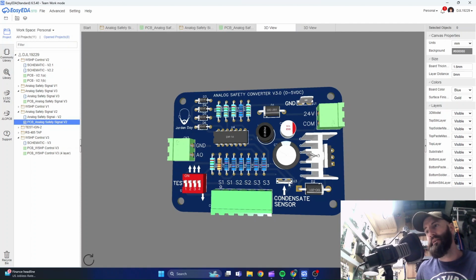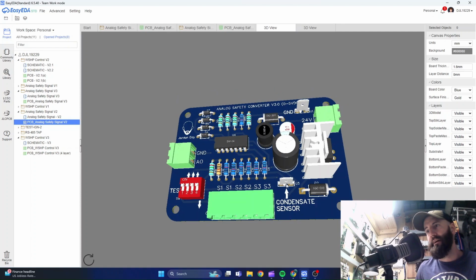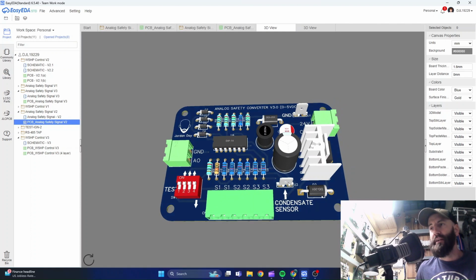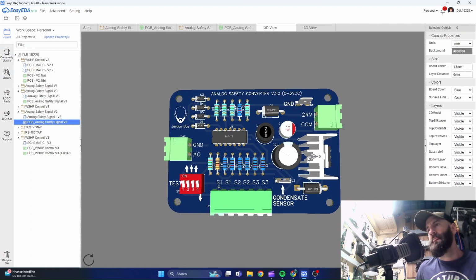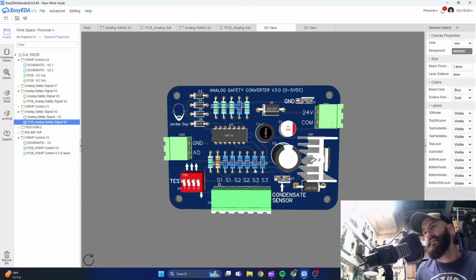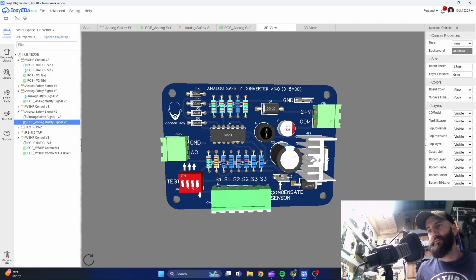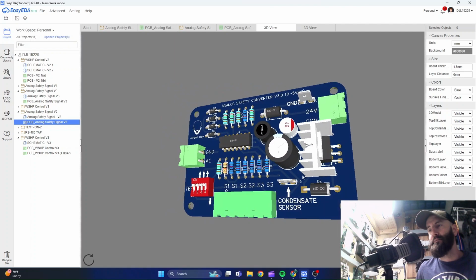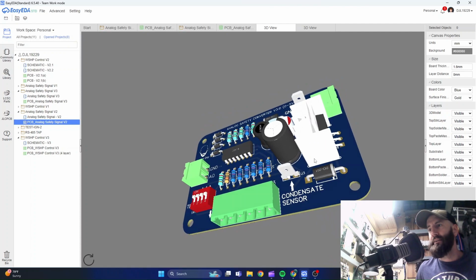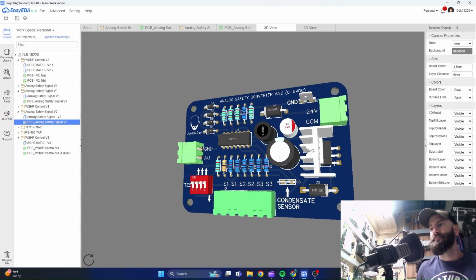So one of the probes would be equal potential with ground, and this condensate sensor is trying to find a path back to that. Now, when you're calculating your resistors, you want to keep in mind that the conductivity of condensate is much lower than just tap water. So if you're doing some bench experiments, don't expect to get the same type of conductivity in your condensate.